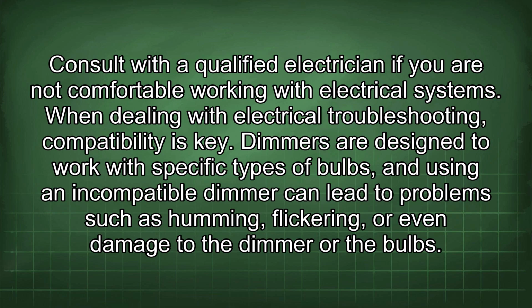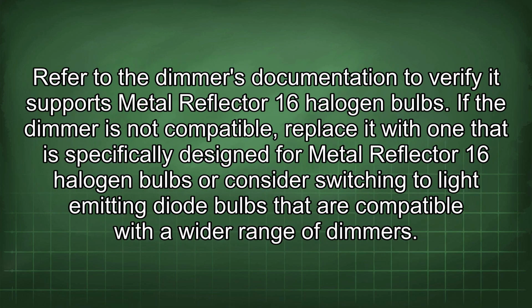When dealing with electrical troubleshooting, compatibility is key. Dimmers are designed to work with specific types of bulbs, and using an incompatible dimmer can lead to problems such as humming, flickering, or even damage to the dimmer or the bulbs. Refer to the dimmer's documentation to verify it supports metal reflector 16 halogen bulbs. If the dimmer is not compatible, replace it with one that is specifically designed for metal reflector 16 halogen bulbs, or consider switching to light-emitting diode bulbs that are compatible with a wider range of dimmers.